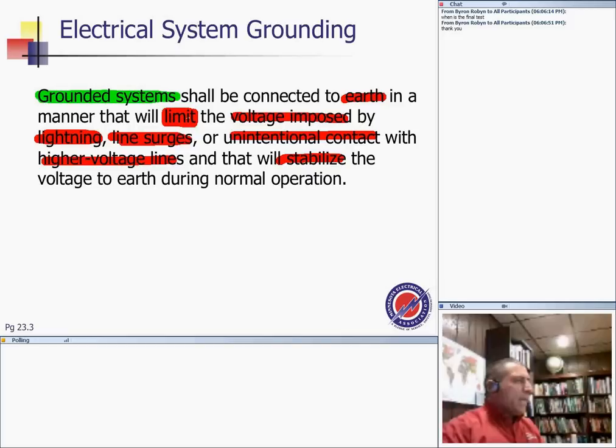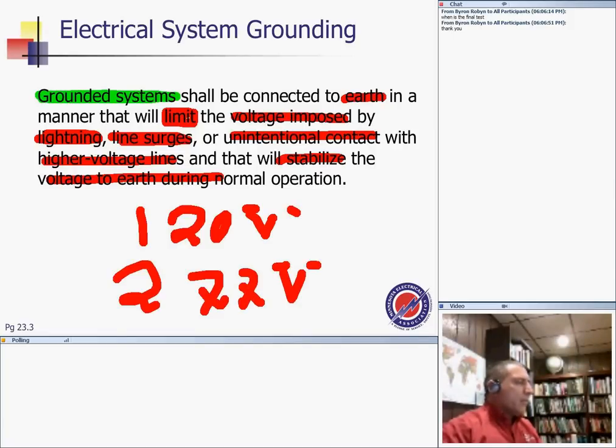And the last reason, stabilize the voltage to earth. That 120 that Joanne was talking about, that we love and we burn equipment at, or the 277 if we're doing commercial, 277 guys, to ground, to ensure that it is a 120 or it is a 277 all the time, we ground the system. Actually, that's why we ground the system. System, not the equipment, the system. I don't see anything here that talks about safety. Grounding the system is, well, in an indirect way for safety, really for the system to work properly and not burn equipment. I guess you can think of a burned plasma TV as also a safety issue. Really, for the equipment to work properly, we ground the system.